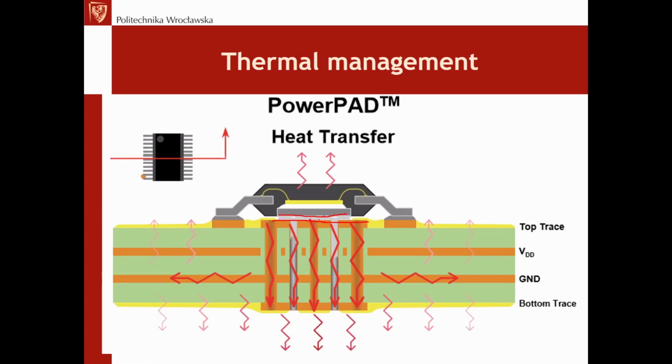Case. So they are not completely flat, which means that if we stick them together, they join on a very limited surface, so the thermal connection is on a very limited surface, and besides these very rare areas of connection, and sometimes just 3 points, we have an empty space here and here. This empty space is filled with air if we don't apply anything special. And the air is a very bad conductor.